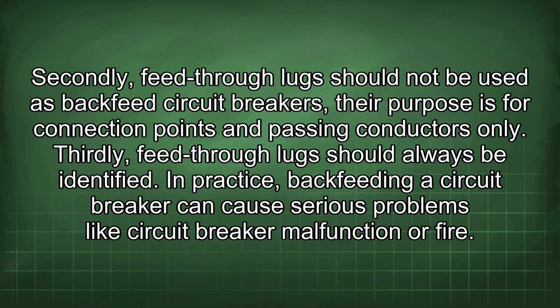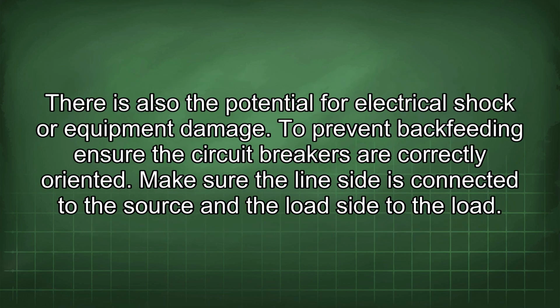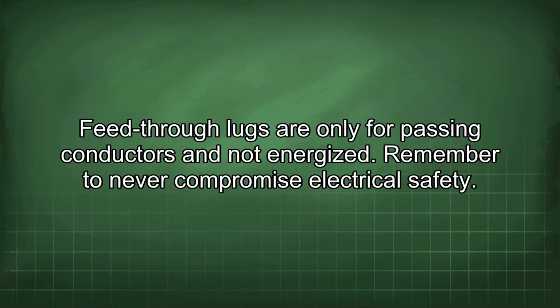In practice, backfeeding a circuit breaker can cause serious problems like circuit breaker malfunction or fire. There is also the potential for electrical shock or equipment damage. To prevent backfeeding, ensure the circuit breakers are correctly oriented. Make sure the line side is connected to the source and the load side to the load. Feed-through lugs are only for passing conductors and not energized. Remember to never compromise electrical safety.